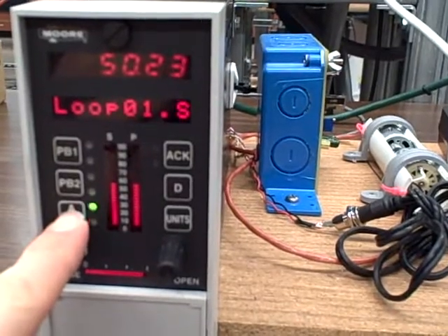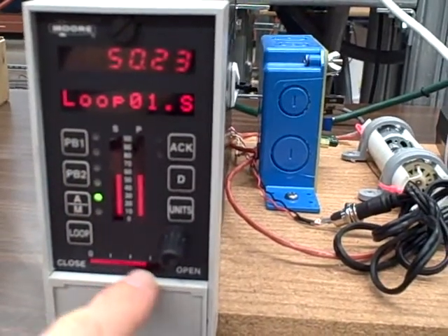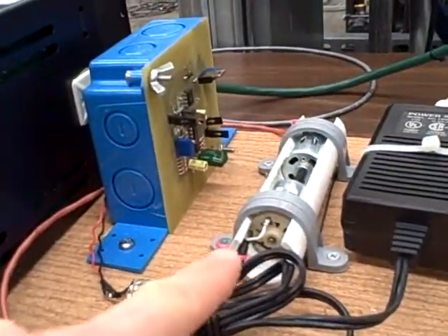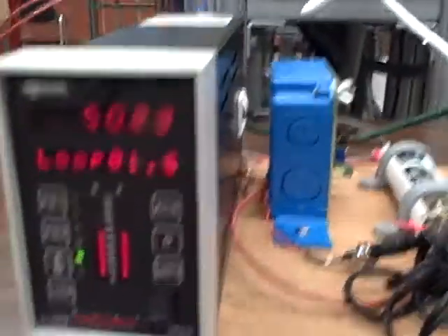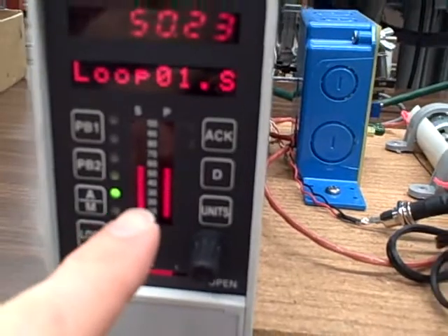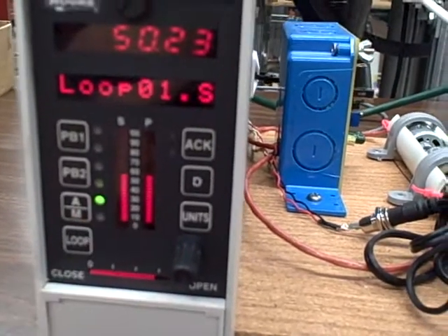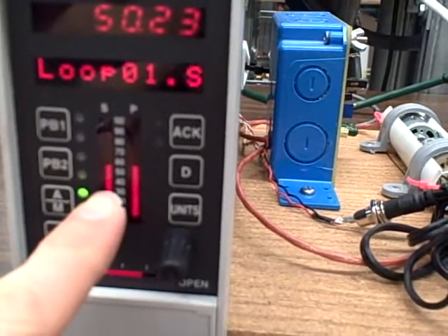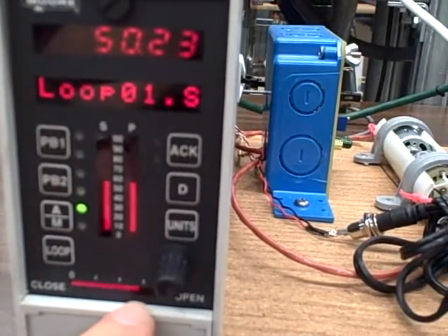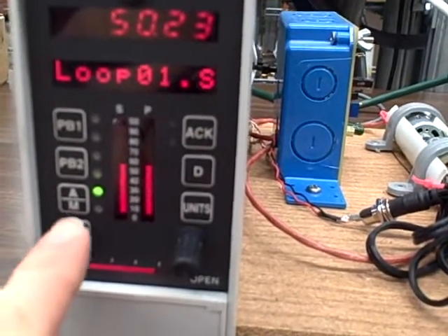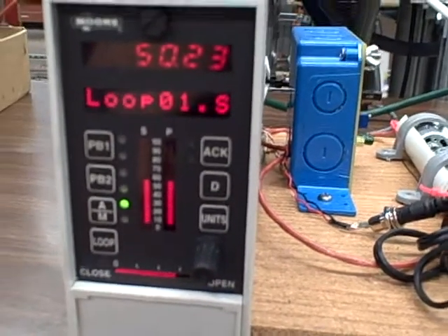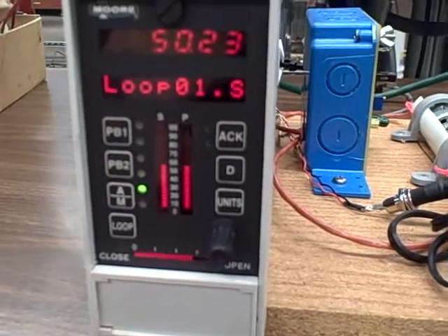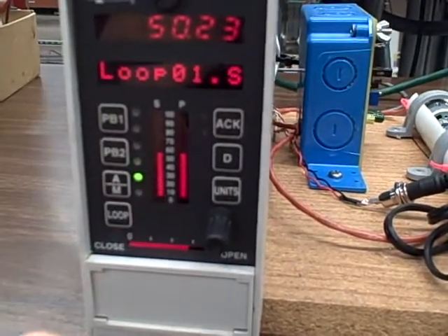When I go into automatic mode, now the controller will make adjustments to the output signal. That is, to make adjustments to the amount of power sent to the motor according to what it sees for the error, the difference between process variable and set point. Right now there is zero error. The process variable and set point are equal to each other, and the output signal here has been established by my former adjustments in manual mode. So right now there is zero error, or we would say zero offset between process variable and set point.